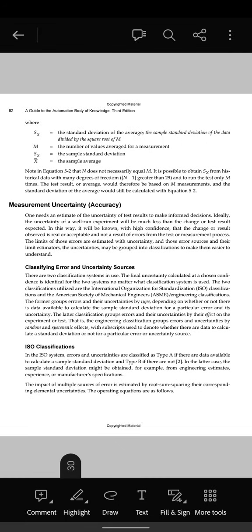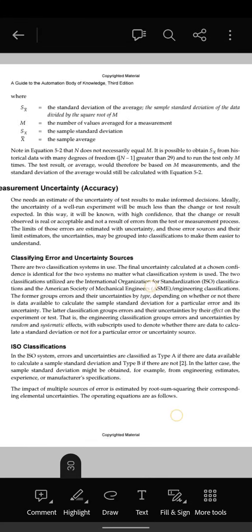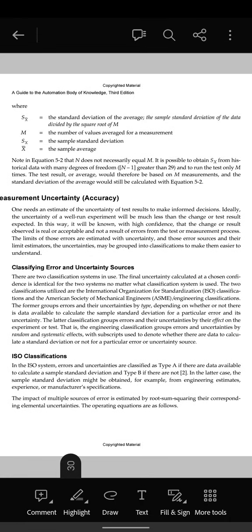ISO classification. In the ISO system, errors and uncertainties are classified as type A if there are data available to calculate a sample standard deviation, and type B if there are not. In the latter case, the sample standard deviation might be obtained, for example, from engineering estimate, experience, or manufacturer's specification. The impact of multiple sources of error is estimated by root sum squaring their corresponding elemental uncertainties. The operating equations are as follows.